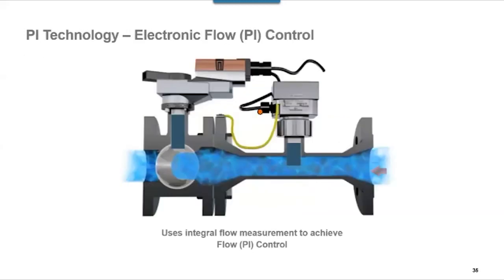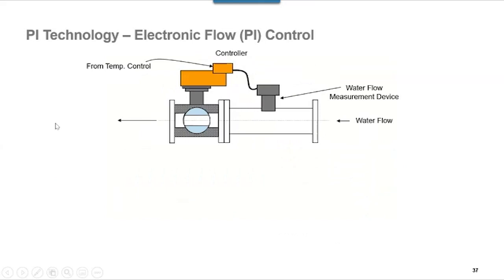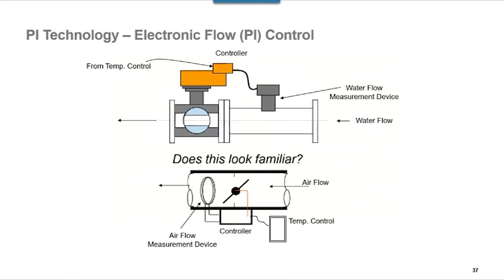With the electronic PI valve, you feed your control signal into the product. So the smart actuator is getting the signal. Programmed into this are the valve curves. The valve compares the actual flow that's occurring across this valve. If the flow is greater than a 5% tolerance, it will reposition itself back to go within a 1% tolerance. So again, it knows where the flow should be, where the flow is, and adjusts the actual flow, which in turn compensates for the pressure variations across the valve. Or as Brian alluded to a moment ago, it's a pressure independent VAV box for water. Same concept, same sequencing, just 2 different mediums.